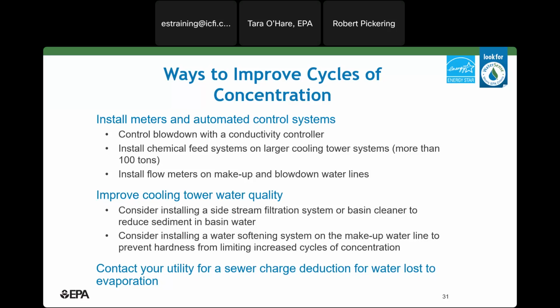Taking steps to improve water quality, such as side stream filtration or basin cleaning to remove sediment, can also offer efficiency improvements. In addition, water softening, if water hardness is a problem in your area, can allow you to increase your cycles of concentration. Your treatment vendor can often advise you on these types of options.